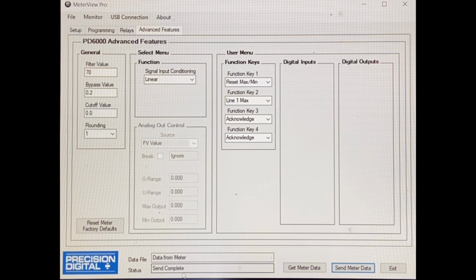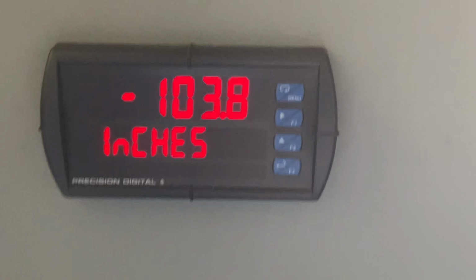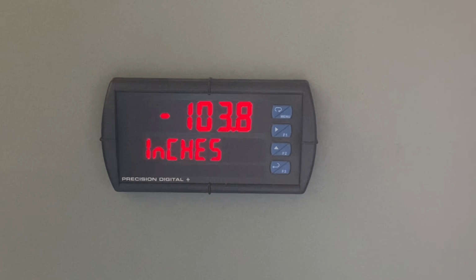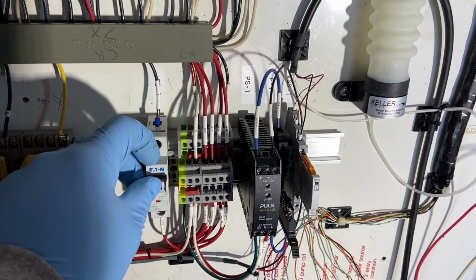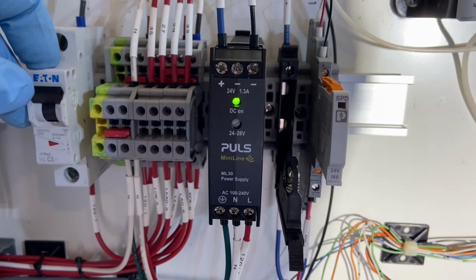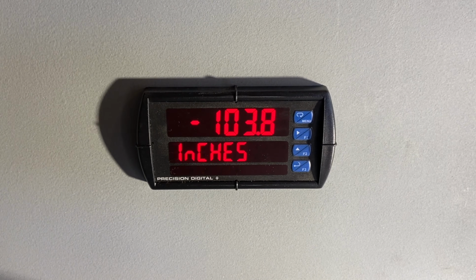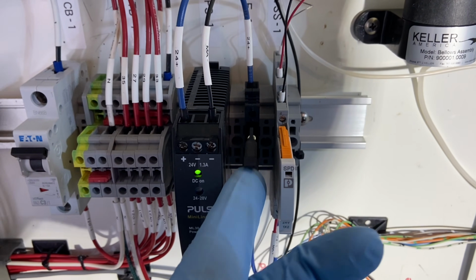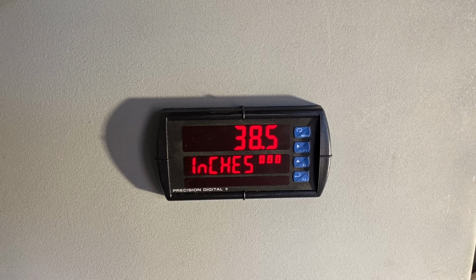Then we're going to send our meter data and make sure it worked. Looks like it did because the display is reading in inches instead of whatever the default was, so we definitely made a successful change. We'll go ahead and unplug our laptop and then turn our power on. This will power up the display with 120 and the power supply for the milliamp loop.